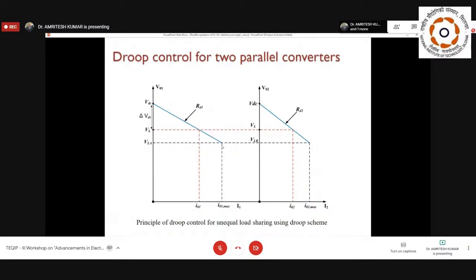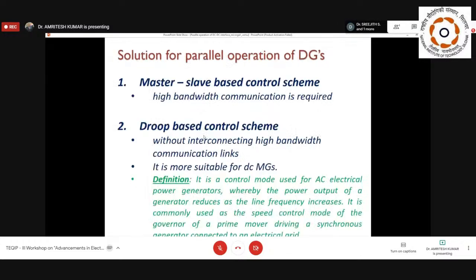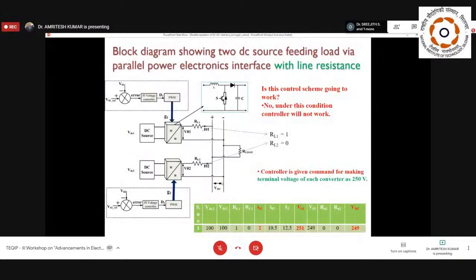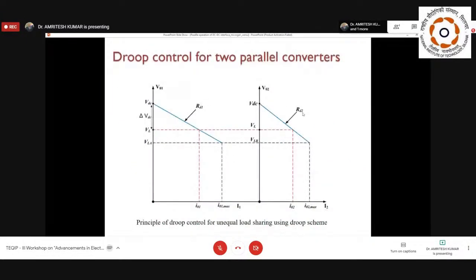This droop curve is decided by the ratings of the converters, and it gives you values called RD1 and RD2. This is the droop resistance, and these are all virtual resistances. RD1 and RD2 are not part of your actual line resistance; the line resistances we have seen are different from RD1 and RD2. This is a virtual droop resistance that we incorporate into our system. Initially we were keeping the reference DC link as VDC. Now, based on the current we derive from each converter, we are going to provide some droop.